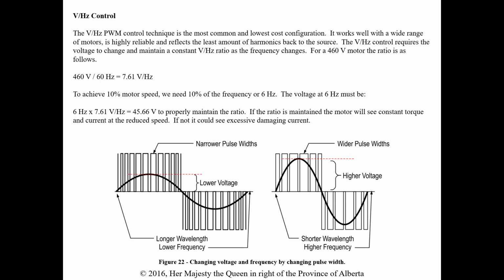Then they talk about the volts per hertz control. The volts per hertz pulse width modulation control technique is the most common and lowest cost configuration. It works well with a wide range of motors, highly reliable, and reflects the least amount of harmonics back to the source. So the volts per hertz control requires the voltage to change and maintain a constant ratio. So for a 460 volt motor, the ratio is as follows. So if I have 60 hertz, this is how many volts I have per hertz. To achieve 10% motor speed, we need 10% of the frequency, or 6 hertz. So if we're going to have 6 hertz, the amount of voltage that we have based on that ratio is 45.66 volts to maintain that ratio.